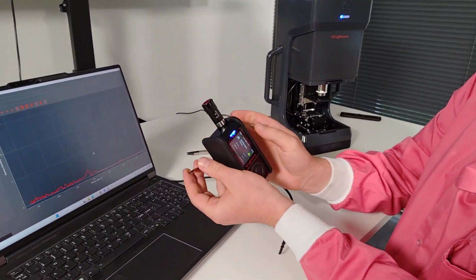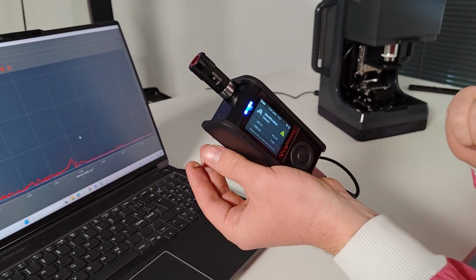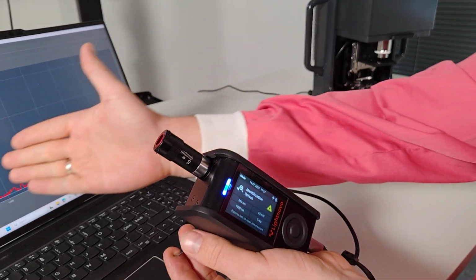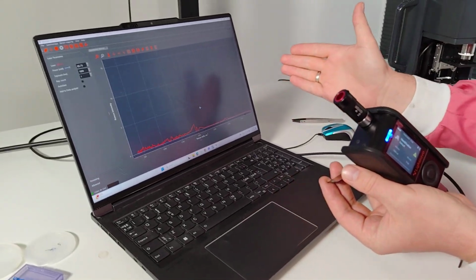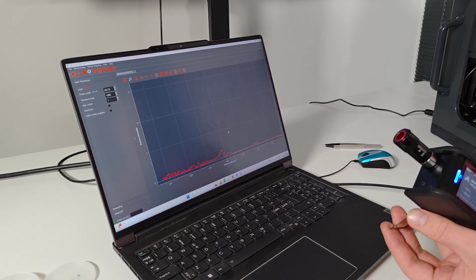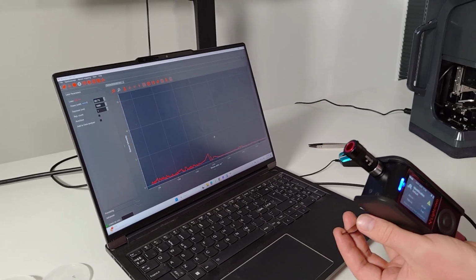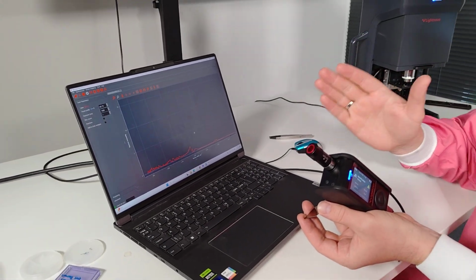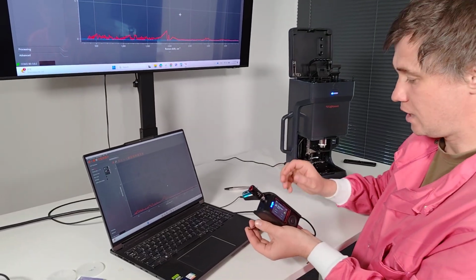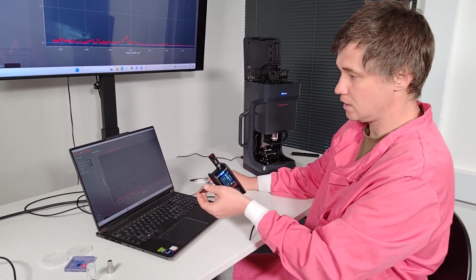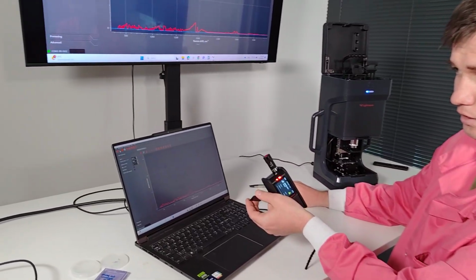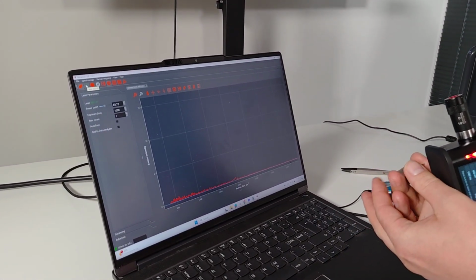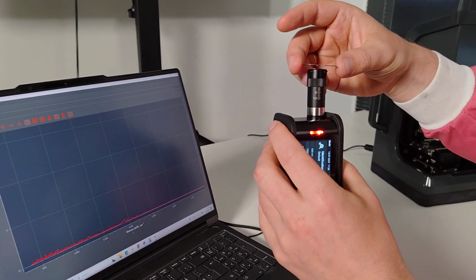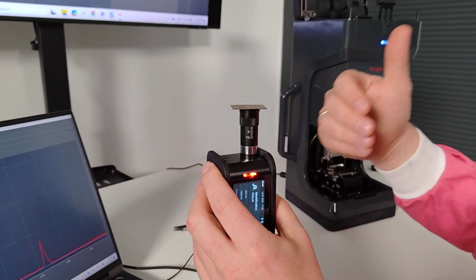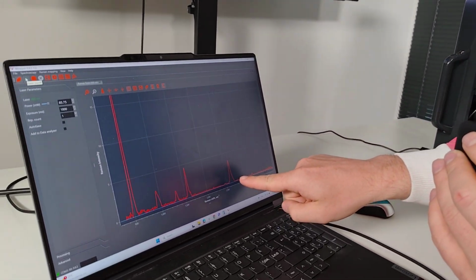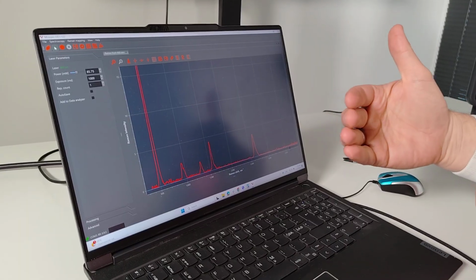Now our spectrometer has inside a 660 nanometers laser, and it can operate in the range from 300 inverse centimeters up to 4000 inverse centimeters with average resolution across the spectrum between 7 to 8 inverse centimeters. And this way, let's say I'm turning on the laser light, and I'm placing on top of the probe a graphene sample. And you can see immediately how the spectra of graphene appear.